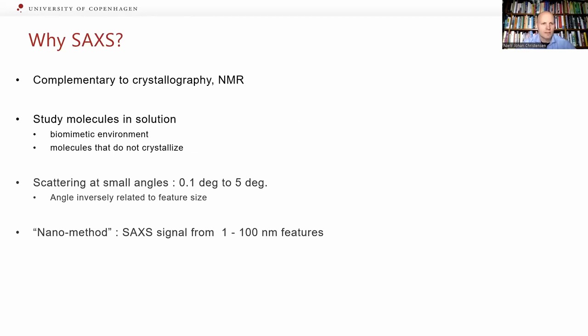Why SAXS? SAXS is a complementary technique to crystallography, NMR, and other techniques. It allows the study of molecules in solution in potential biomimetic environments, also of molecules that do not crystallize. It studies scattering at small angles — typically 0.1 to 5 degrees — and this scattering angle is inversely related to the feature size. It is inherently a nanomethod since the feature sizes studied are from 1 nanometer to 100 nanometers, typically.